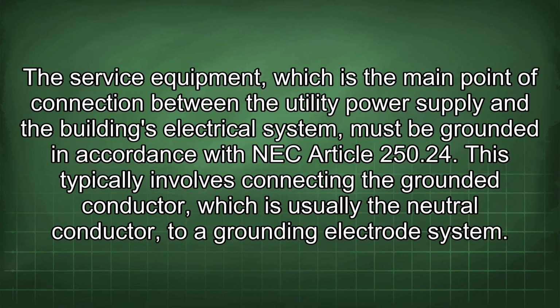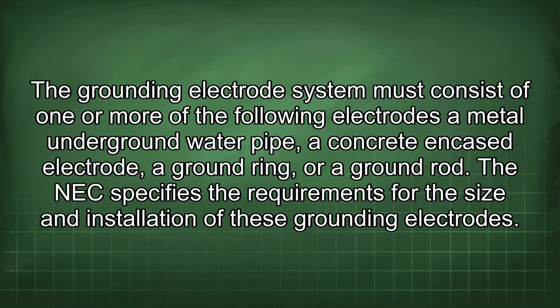The service equipment, which is the main point of connection between the utility power supply and the building's electrical system, must be grounded in accordance with NEC Article 250.24. This typically involves connecting the grounded conductor, which is usually the neutral conductor, to a grounding electrode system. The grounding electrode system must consist of one or more of the following electrodes: a metal underground water pipe, a concrete encased electrode, a ground ring, or a ground rod. The NEC specifies the requirements for the size and installation of these grounding electrodes.